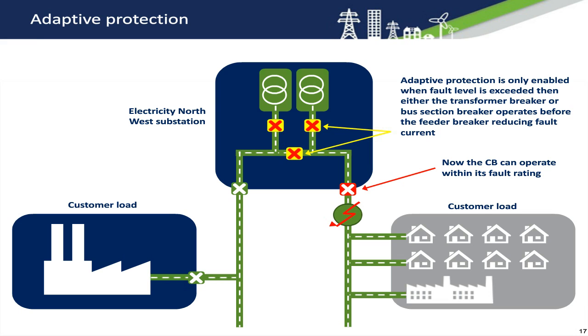Adaptive protection alters the sequence in which our network breakers operate. The red squiggly arrow on the right depicts a fault on our network. All protective devices start to operate, but the closest one to the fault operates first and disconnects customers of the network beyond the fault.